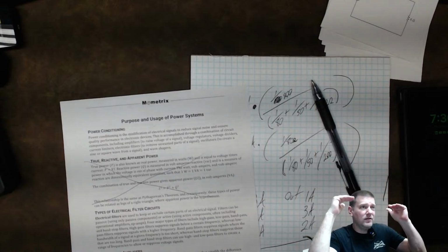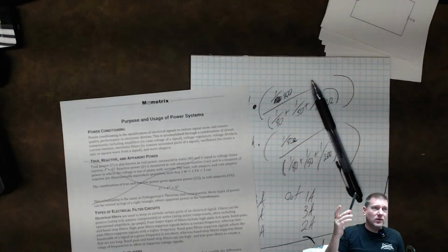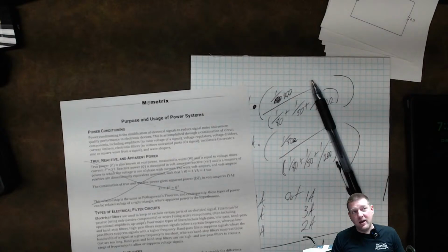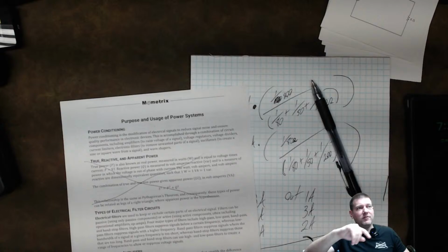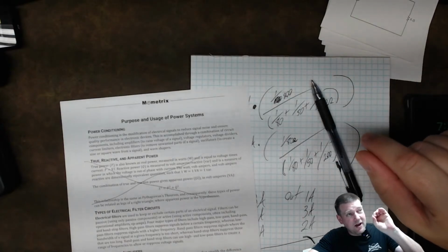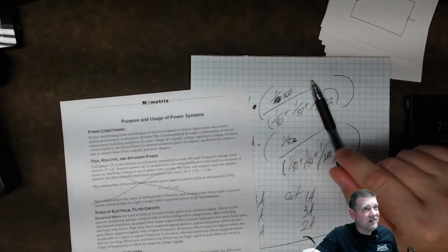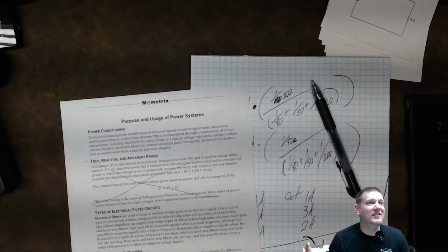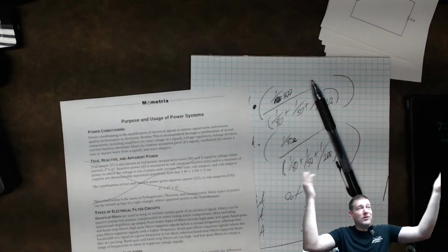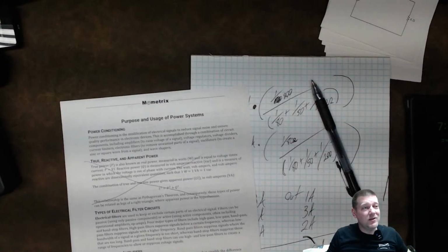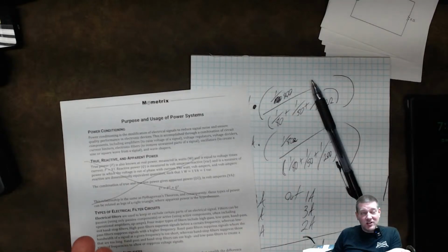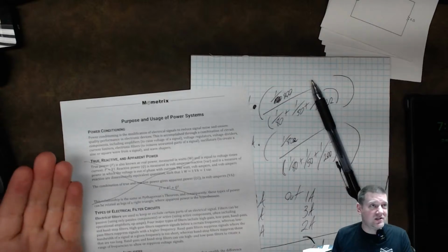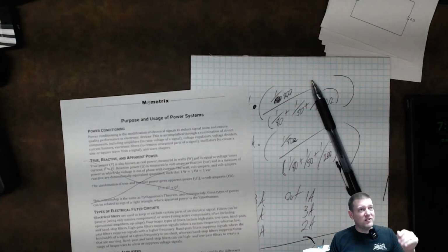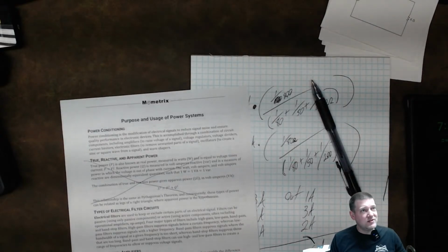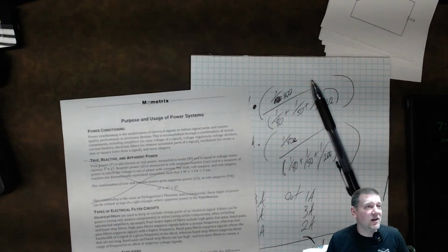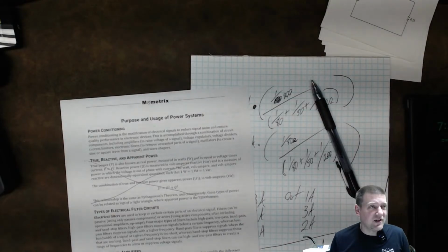LEDs and other devices tend to turn on and off at 60 hertz, which can create problems depending on your shutter speed. So any electrical cables running around certain sources will have filter circuits to notch out that 60 hertz, so it doesn't end up on things like your ECG. Your ECG naturally wants to vibrate at 60 hertz because all the lights around you flash at that frequency, and it's basically just an amplifier. But because it has the 60 hertz filter, it notches that out so the other signals can be read cleanly. So you'll see filter circuits in real medical equipment.